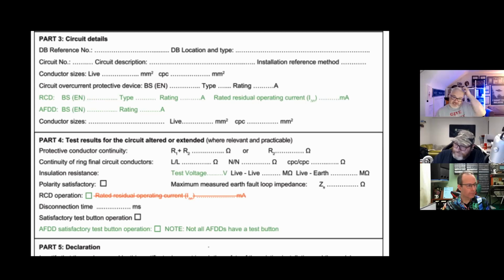AFDD satisfactory test button - note, not all AFDDs have a test button. As Mr. Ward rightly said earlier while we were chewing the fat, a lot of the AFDDs we're purchasing are combined with RCBOs, but there are other ones available as modules that bolt in and connect like a shunt and operate. It's a valid point, although I wouldn't buy one without a test button, to be perfectly frank.